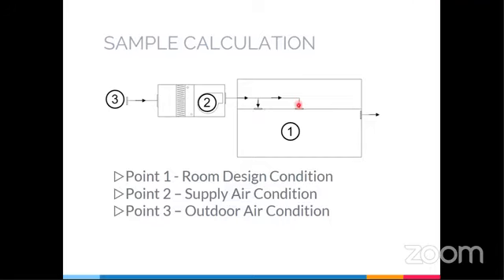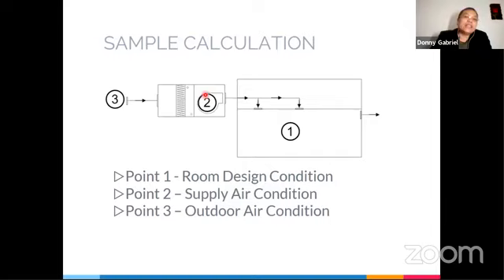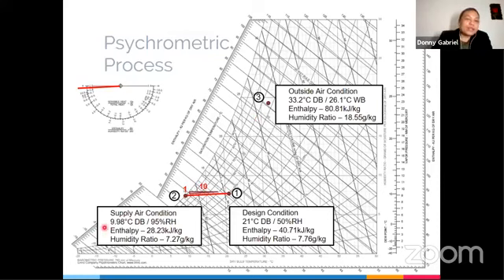So for the duct loss, we did not consider the heat gain from the motor, from the fan. We did not consider. We assume that there's an adiabatic process, or it's insulated. So the condition after the coil is the same as the condition going out to your room. Okay? So we got the 9.98 degrees Celsius and 95% RH. We will get back to this 95% RH, no? But at the moment, we will say it's 100% saturated. We got this from the graphical representation from our design condition, point 1, drawing a parallel line. Then we got this point.